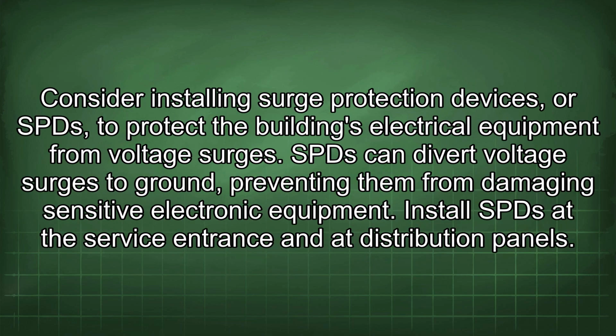Consider installing surge protection devices, or SPDs, to protect the building's electrical equipment from voltage surges. SPDs can divert voltage surges to ground, preventing them from damaging sensitive electronic equipment. Install SPDs at the service entrance and at distribution panels.